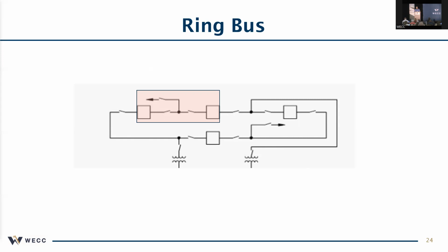I made the assumption one time that no one would ever make a breaker that wouldn't handle the line facility. I was wrong. There are situations out there where we have 1 or 2 breakers that are rated less than the conductor on the line. So we can't make any assumptions. So we need to ask.